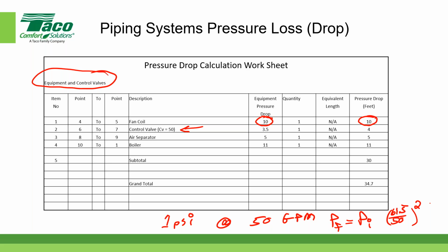Look at that. Yep. So if I take 61.5 divided by 50, that's approximately 1.23, and I square that, well, that comes out to approximately 1.5 times the initial pressure of 1 PSI. My new pressure drop is equal to 1.5, and I've multiplied that by 2.31 to convert it into feet. That comes out to approximately 3.5 feet. And look at that, magically, it's right there at 3.5 feet. So that's how I can convert my pressure drop given the specific information on a control valve. If I'm flowing more than what the CV value is, I can use this little equation down here and calculate the pressure drop. And in my little example here, I carried it over, I rounded it off to 4 feet. So the actual calculation was 3.5, but I rounded it off to 4.